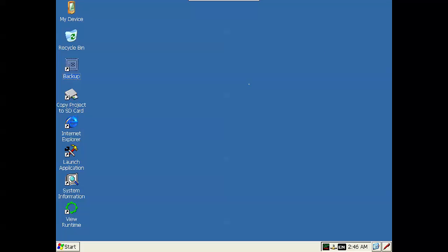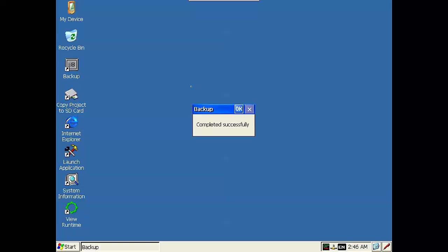Once you've input the setting in the QuickPanel you need to remember to back it up by using the backup icon here on your main screen. If you double click on the backup it says backup completed successfully. This will save all of your QuickPanel settings including the IP address that we just entered into flash memory. Therefore it will be remembered over a power cycle of your QuickPanel.